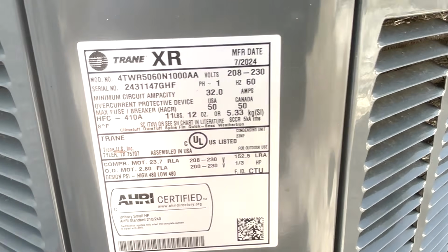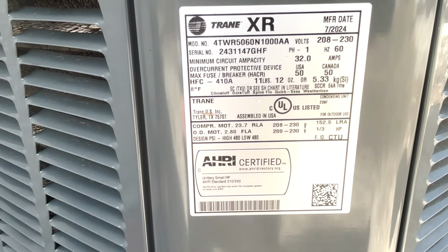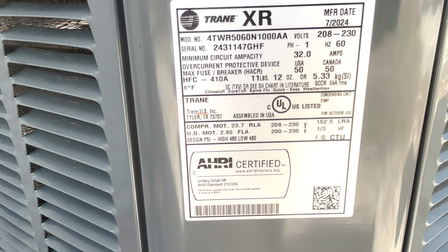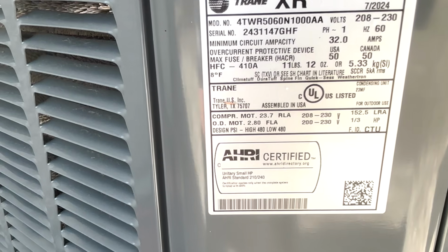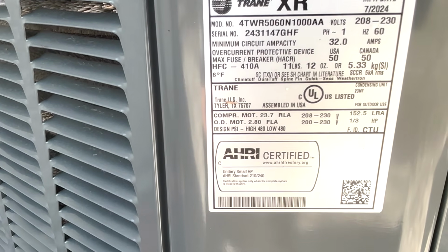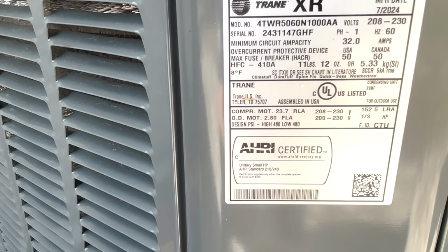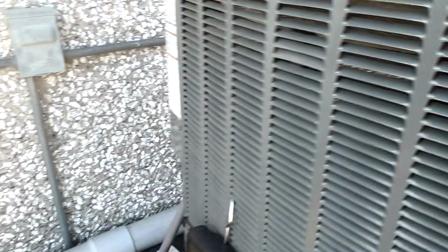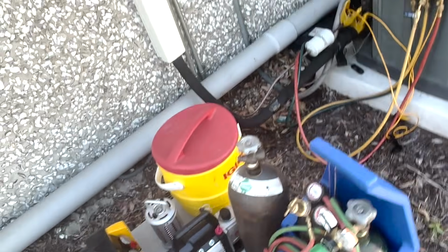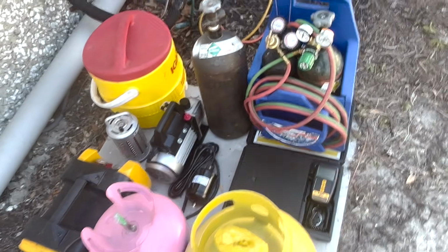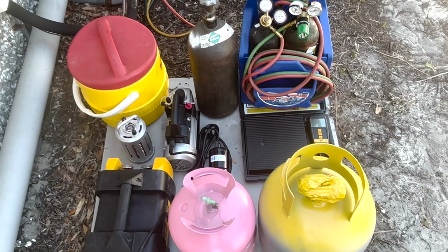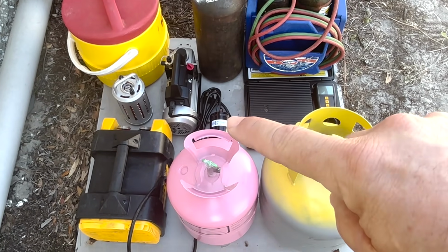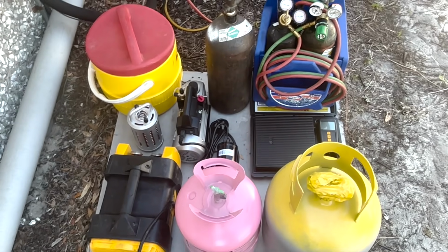If we look over here, we can see that this unit here is a 410A and it holds 11 pounds, 12 ounces, plus the refrigerant line set. So we're definitely more than 12 pounds on this. And with that, it's important to scale in this refrigerant, and then we can balance the superheat and subcools past that. But if you're wondering what tools you would need just to do this job and put that dryer in there, it's quite a bit.